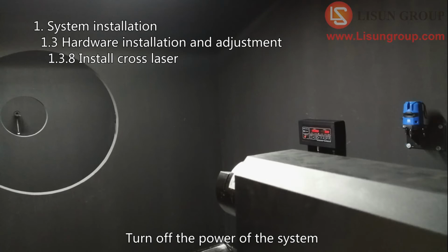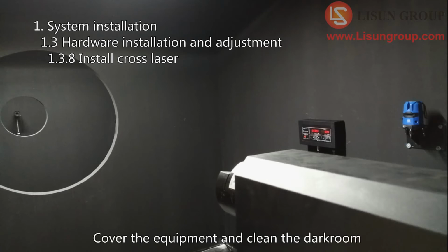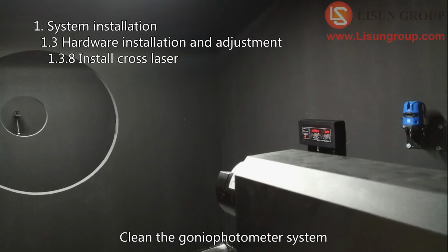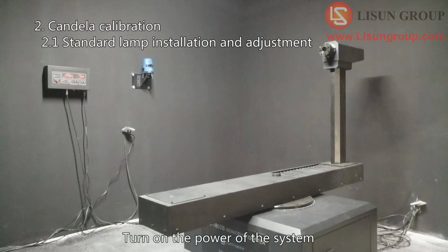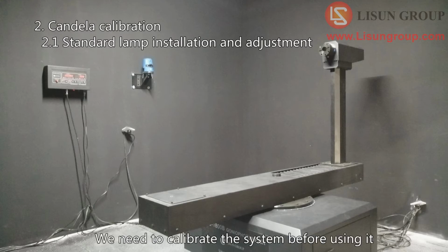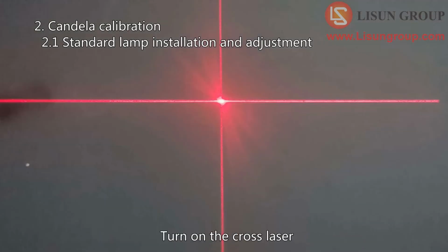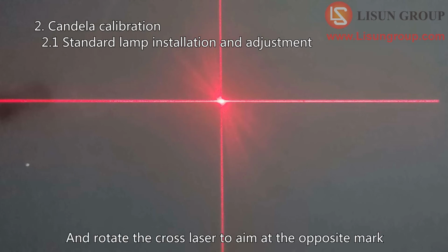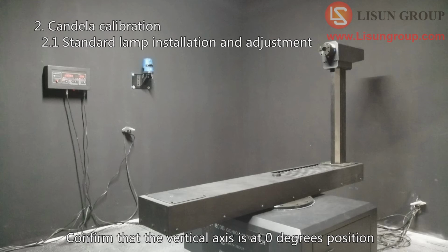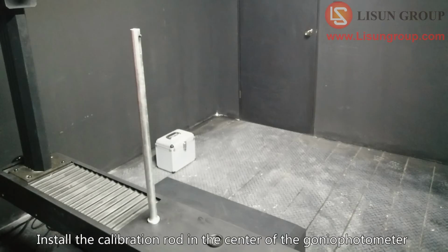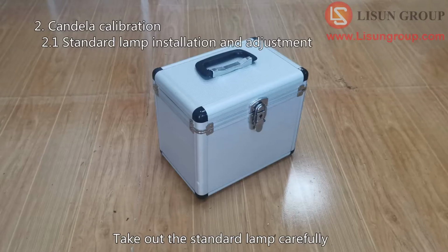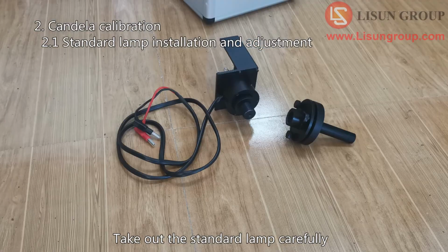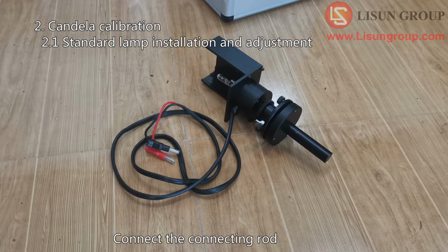Turn off the power of the system. Cover the equipment and clean the darkroom. Clean the goniophotometer system. Turn on the power of the system. We need to calibrate the system before using it. Turn on the cross laser, and rotate the cross laser to aim at the opposite mark. Confirm that the vertical axis is at 0 degrees position. Install the calibration rod in the center of the goniophotometer. Take out the standard lamp carefully. Connect the connecting rod.